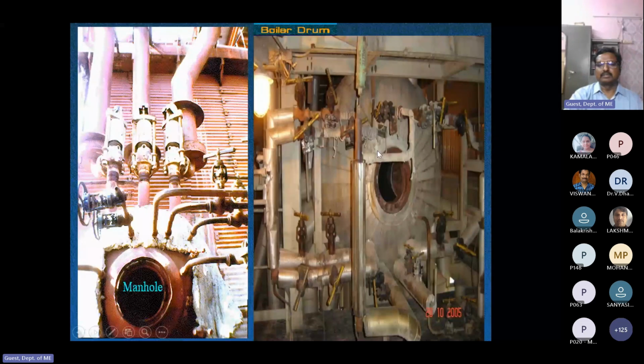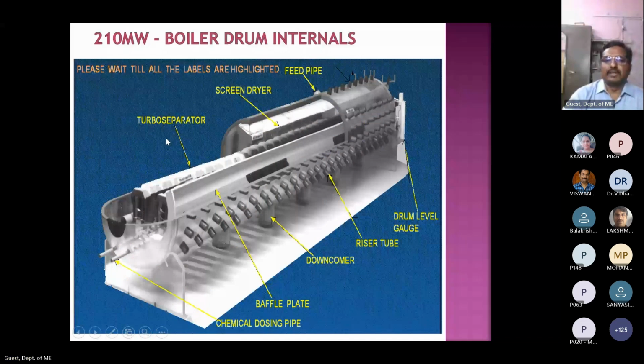This is the actual photograph of the boiler in this plant. The boiler looks like this, with total insulation. There are hydrastep units for measuring the level in the boiler. There are different lines and safety valves. Inside the boiler, these are the general arrangements. They call them turbo separators and screen dryers, used for separating. For example, as I already told, the bottom half of the drum is filled with water and the top half is filled with steam. In the steam, there is a chance of containing moisture, so that moisture is removed with the help of turbo separators and screen dryers.